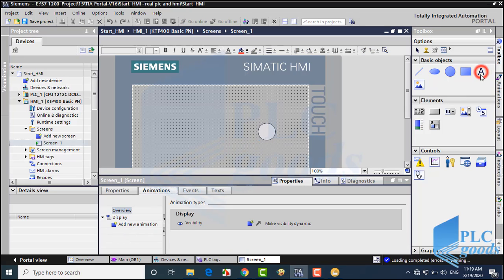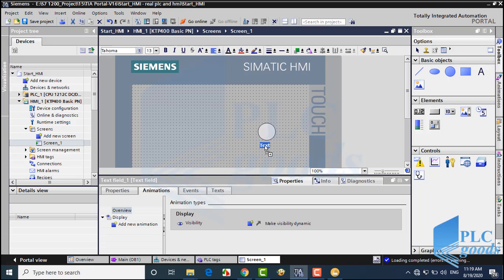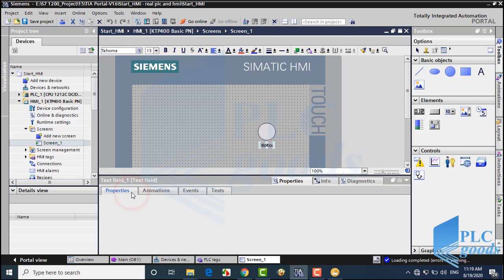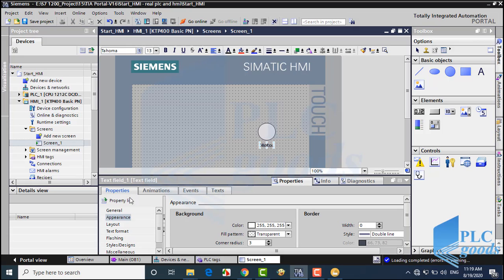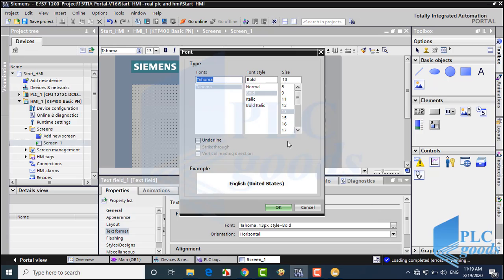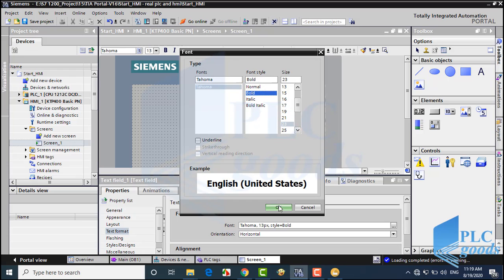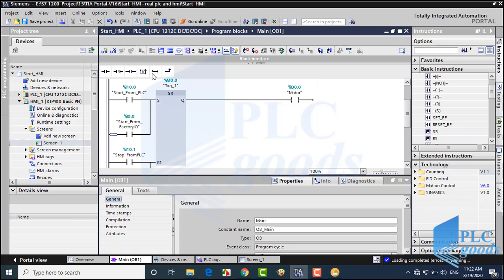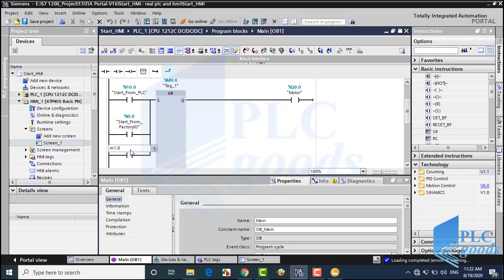Also, let me insert motor text. Now, how can we turn on and off the output from the HMI? Pay attention — HMI can't change the PLC inputs, but it can modify PLC memory. So I can use two contacts with a bit of memory address, which can be changed by the HMI.